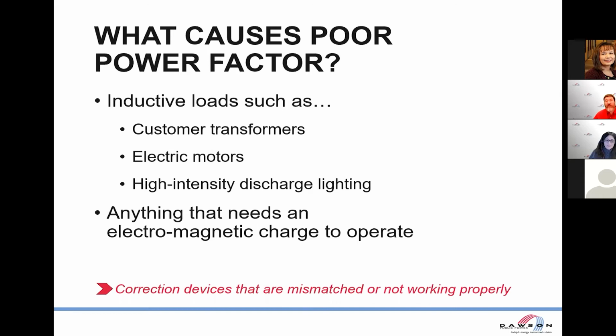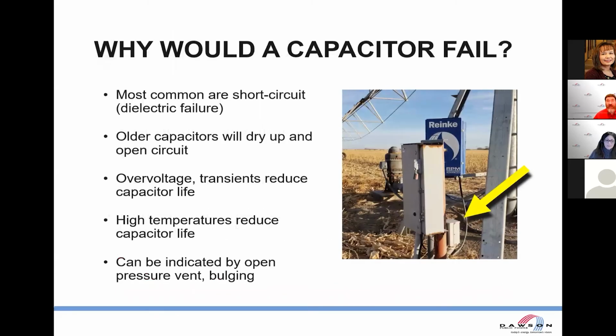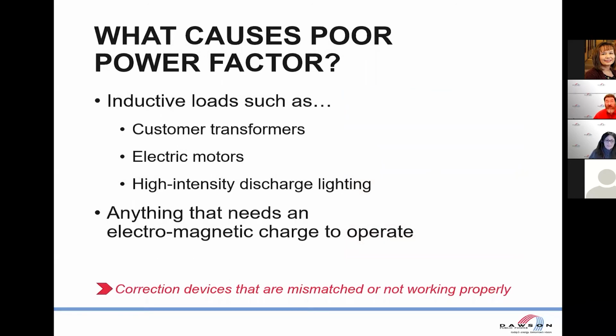There's probably not much of this on customer service, and if so, it's probably not a major contributor to your power factor compared to your motor. But high intensity discharge lighting, so those are like yard lights, the high pressure sodium or old mercury vapor ones especially. Basically anything that needs an electromagnetic charge to operate is going to reduce power factor. If you've got a correction device that's overcompensating, so it's putting you over 100%, that also could potentially be affecting your power factor. Basically, if your capacitor is way too large for the motor it's paired with.